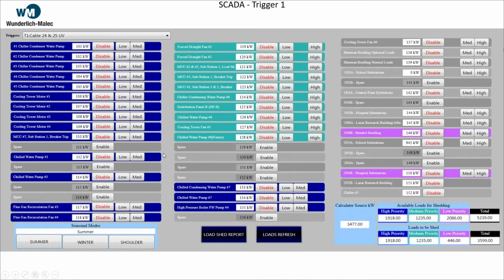All right, thank you, Micah. So what we have here is a screen that we've developed for our custom load shed system. And what it provides is a very configurable interface for our operators. In the upper left, you'll see triggers. And what we mean by trigger are different events that would be loss of generation, such as the generators or the utility source. So for this particular system, it's selected to a loss of utility. And what the screen is showing is based on the loads that are enabled, it's selecting and showing you in real time what's going to actually be shed based on what the system is calculating needs to be shed to maintain a stable system. In addition to being able to enable and disable the loads, you can set the priorities for which loads get shed first.